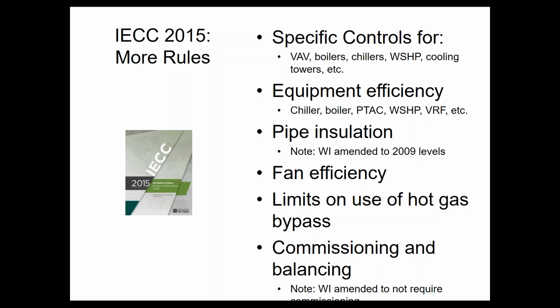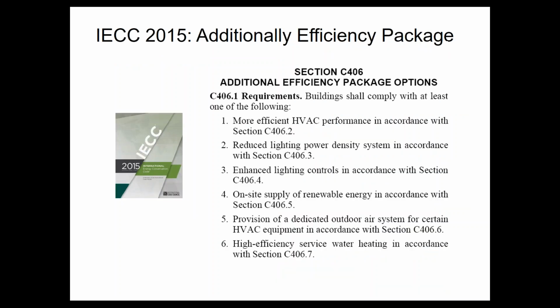Commissioning is required, balancing is required. Once again, Wisconsin has an amendment on that. You do not have to commission the systems if you're in Wisconsin per the code. You might still want to do it. It's still a good idea, but you're not forced into it. In Illinois, you are forced to do it.